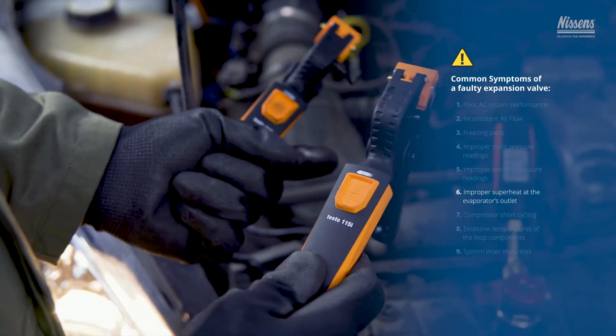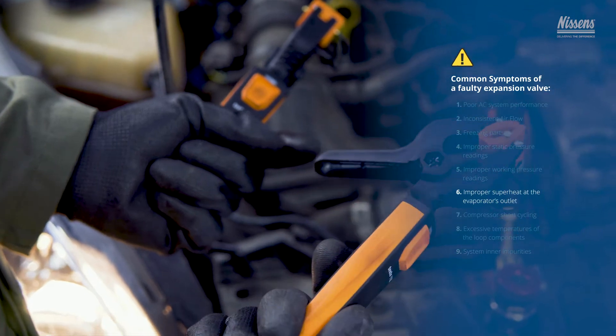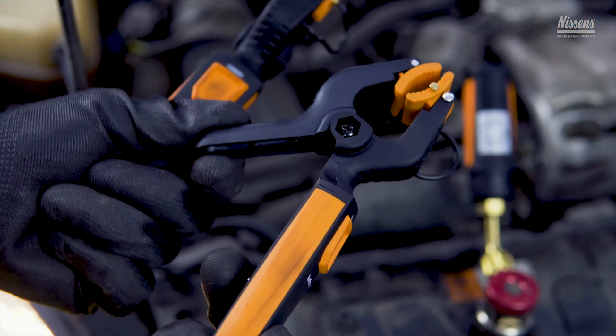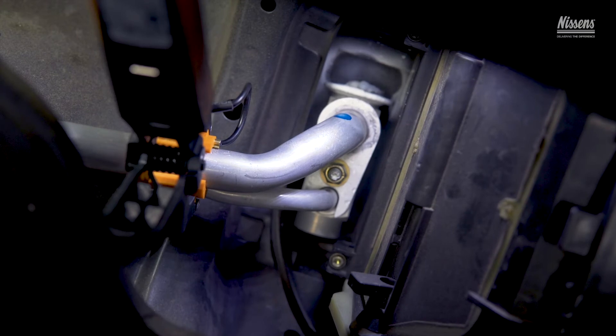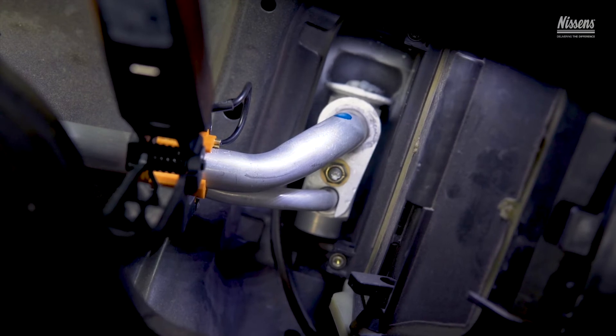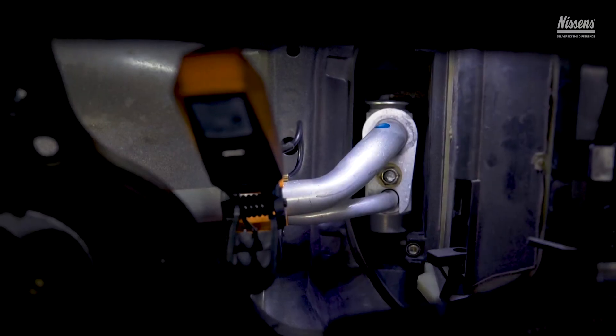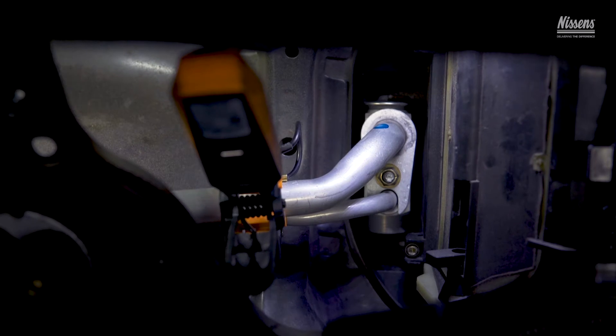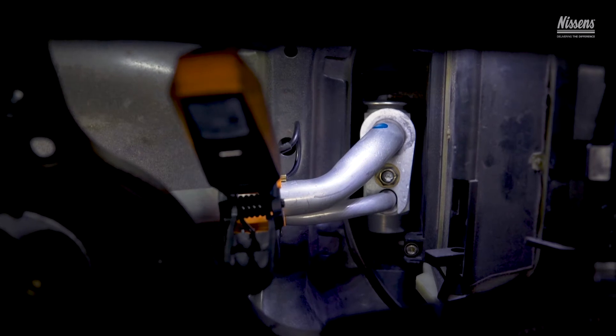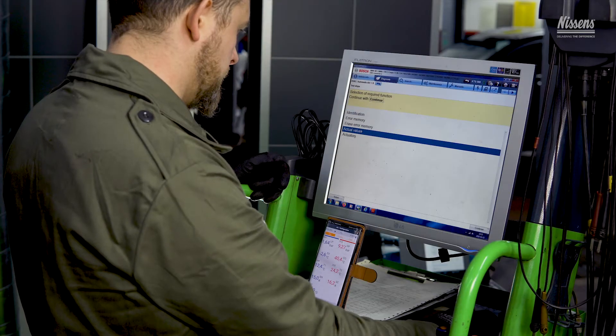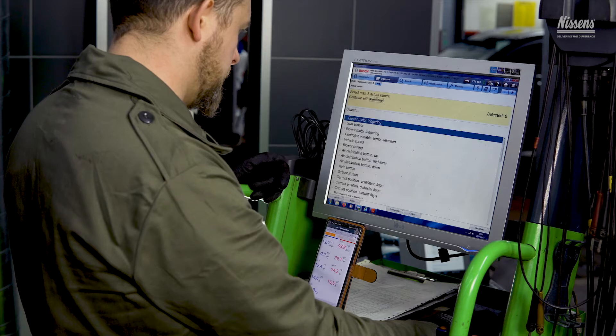Improper superheat temperature at the evaporator's outlet: the superheat value measured at the evaporator's outlet can help you conclude whether the TXV, and thus the system, operates optimally. Link the temperature readings with the refrigerant's respective pressure-temperature table.